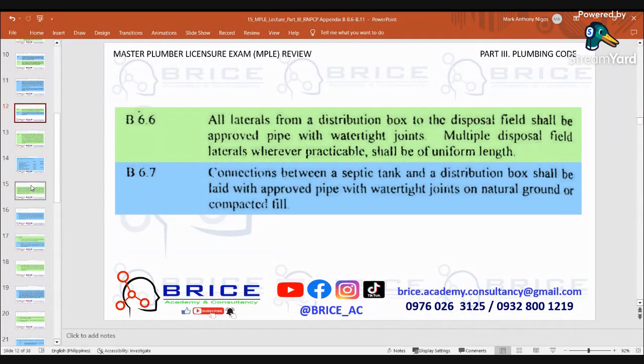All laterals from a distribution box to the disposal field shall be approved pipe with watertight joints. Multiple disposal field laterals, wherever practicable, shall be of uniform length. Connections between a septic tank and a distribution box shall be laid with approved pipe with watertight joints on natural ground or compacted fill.